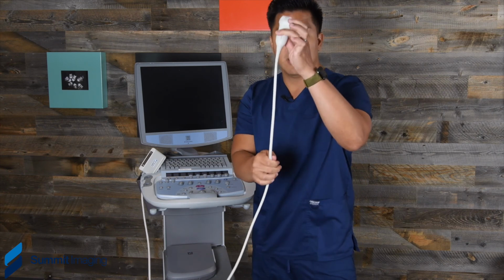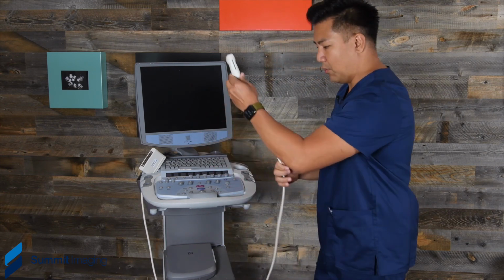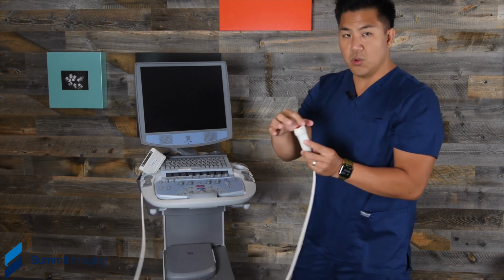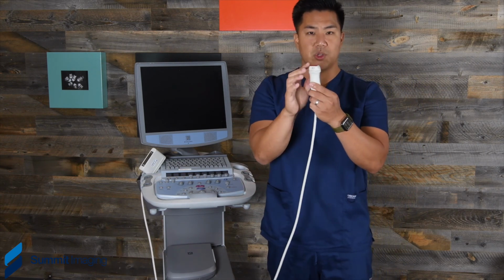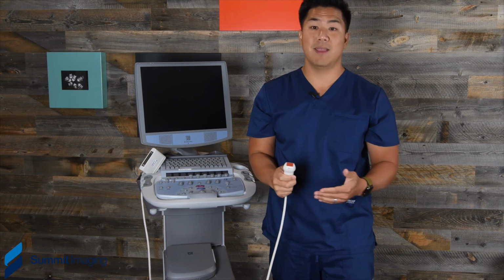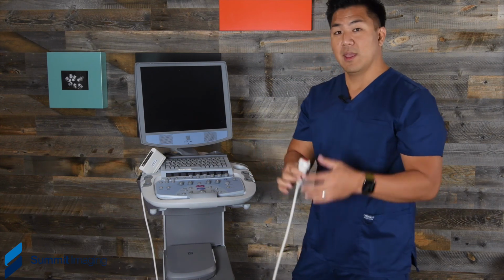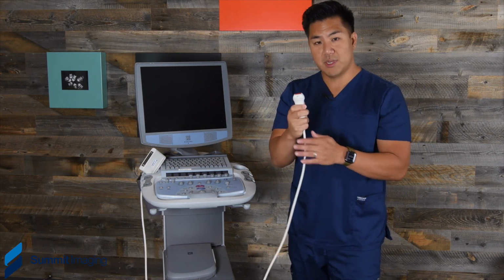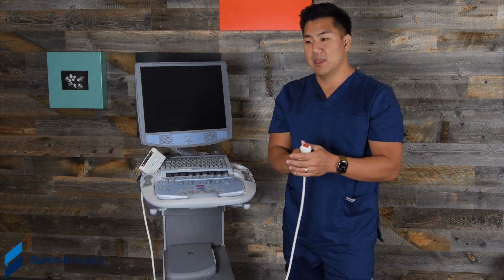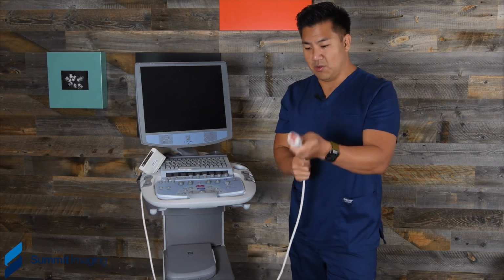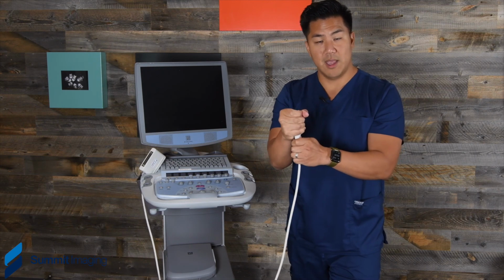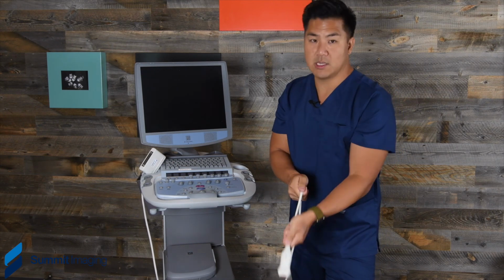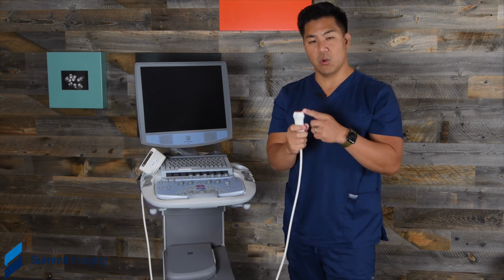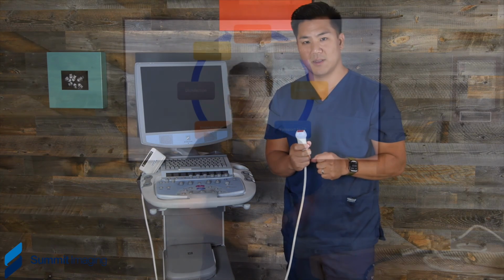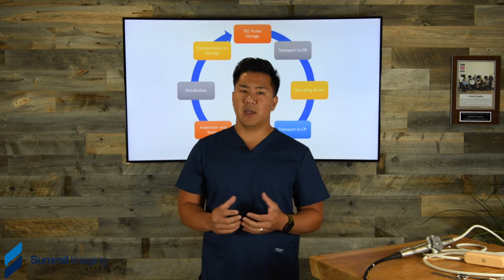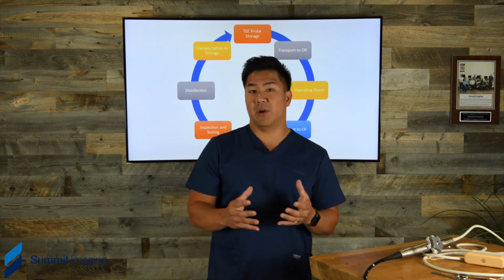You catch it here, the force comes down, and when the force comes down and hits the surface, you knock the side of all the microcircuits around the crystal, causing a massive amount of damage. So keep hold of this, protect this, and if it starts slipping, prevent yourself from grabbing the cable. Grab the head of the probe so it doesn't swing down and really impact something that will cause damage to the internal electronics. Yep. And so in the OR, in clinical use, there's a variety of other factors.